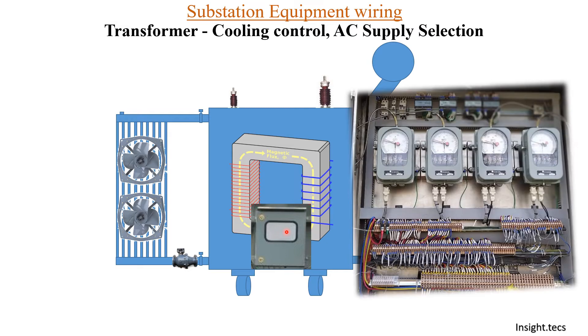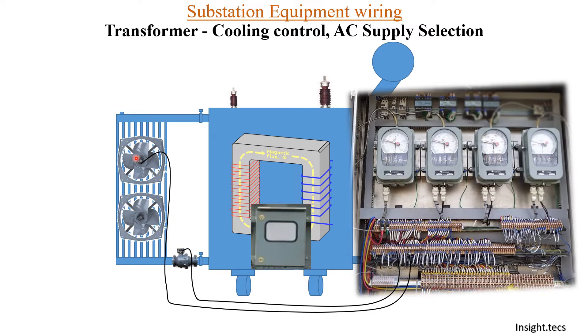We have this MK box, and inside this box you can see different kinds of meters that are continuously monitoring the oil temperature indication. The other meters are the winding temperature indications for each phase individually — R phase, Y phase, and B phase. All this wiring is done in this MK box. There is specific wiring done for the pump and specific wiring for the fan, so that whenever the temperature rises above a certain degree, the fans turn on automatically. When the winding temperature rises above a certain temperature, the pump has to automatically start. Whenever the temperature comes down after a certain degree, they will automatically turn off.